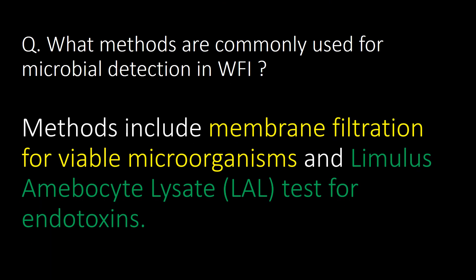What methods are commonly used for microbial detection in WFI? Methods include membrane filtration for viable microorganisms and the Limulus Amoebocyte Lysate (LAL) test for endotoxins.